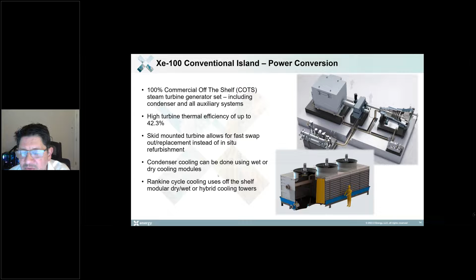For condenser cooling, we can use anything from something like these forced wet-cooled modules on the bottom right-hand side. In fact, the plant that we'll be doing for Dow in Seadrift, Texas, will be using air-cooled condensers like at Matimba and Medupi and Kusile, because it is a water-strained area. Obviously that will drop the efficiency a bit, but we believe that wet cooling is really difficult to get approved in many areas of the world. So having a fully dry cooled solution is a huge benefit as well.